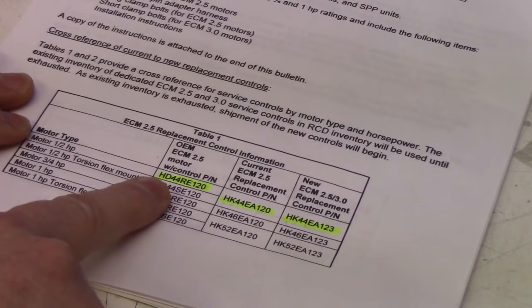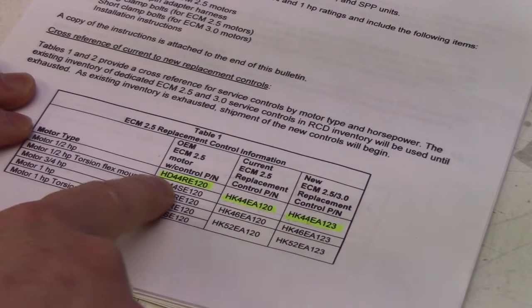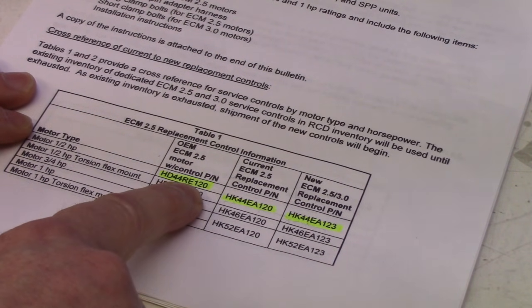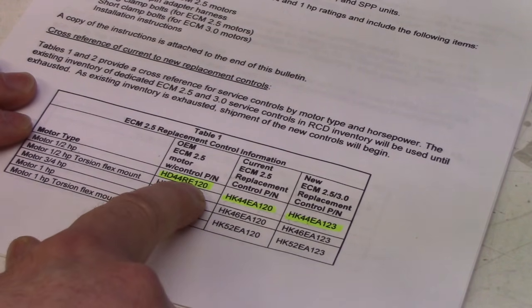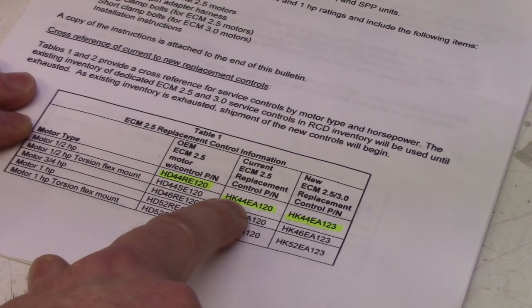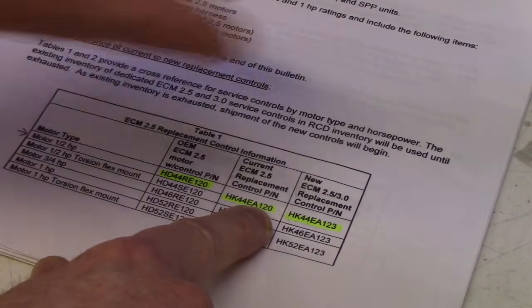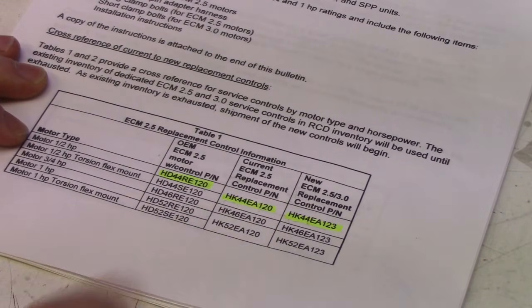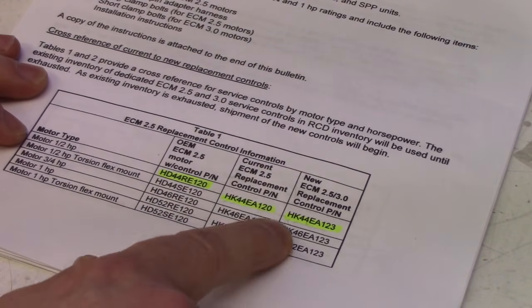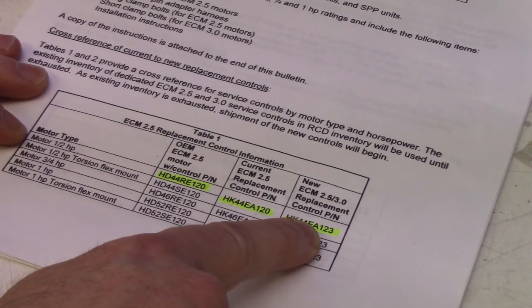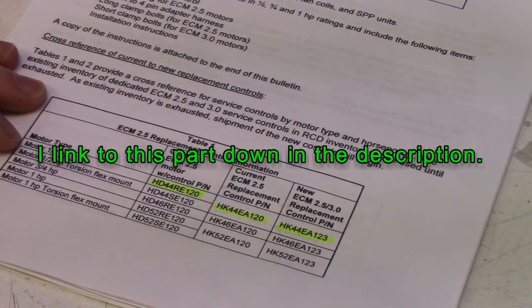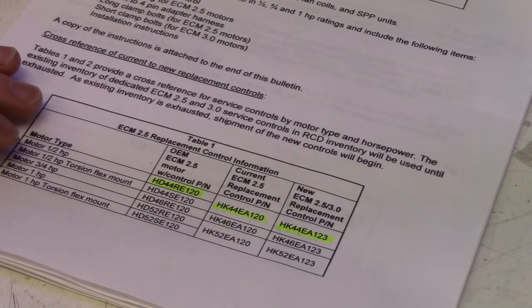Then down here at the bottom it shows what part number our old motor and ECM 2.5 was - it's an HD44RE120. When I look online I can't find them anywhere, not even used. Just the ECM is an HK44EA120, that's the ECM 2.5. Again, can't find them. But it has been replaced with the HK44EA123 ECM - this is actually a 3.0 ECM with an adapter ring and an adapter plug.